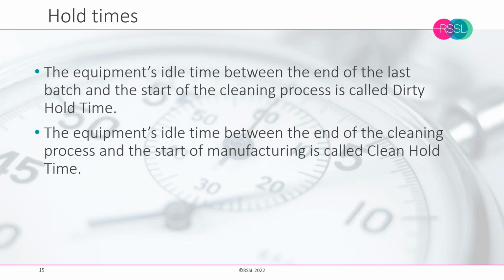And it's been shown that when equipment is left uncleaned, the longer the duration, the more likely that residues attached to the surface become more rigid. And as they dry over a period of time, they become more challenging for the cleaning process. This also presents greater opportunity for microbial growth as well. So exceeding the dirty hold time outside of what's been validated presents a problem. The second area is the equipment's idle time between the end of the cleaning process and the start of manufacturing. And this is the clean hold time. And this is partly influenced by wherever the equipment is stored as well. So the conditions in which it is kept, whether it's subject to excessive humidity, and if it's anywhere near dirty equipment and so on. So there are various control factors to consider as well.